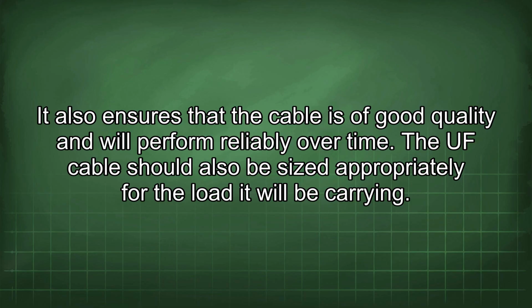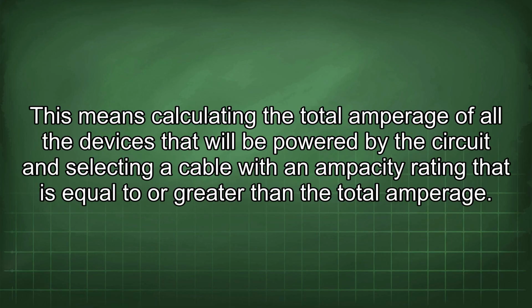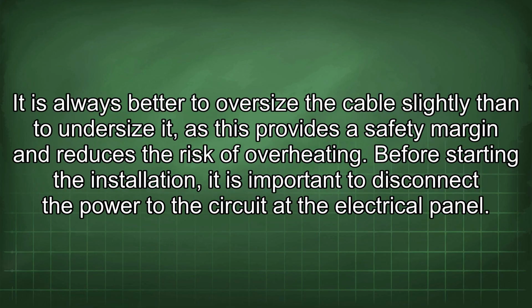The UF cable should also be sized appropriately for the load it will be carrying. This means calculating the total amperage of all the devices that will be powered by the circuit and selecting a cable with an ampacity rating that is equal to or greater than the total amperage. It is always better to oversize the cable slightly than to undersize it, as this provides a safety margin and reduces the risk of overheating.